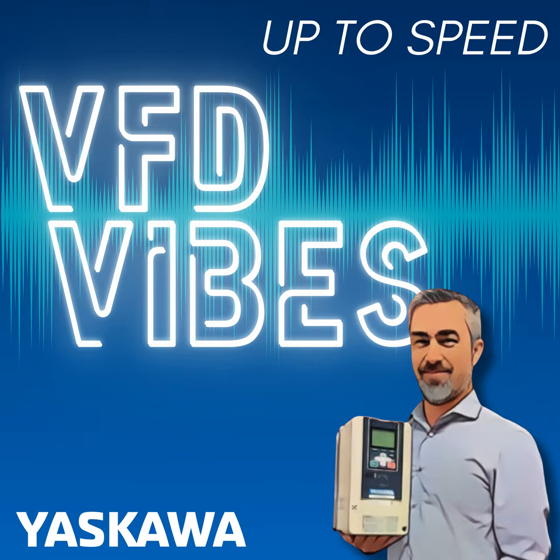S1 and SN, a maintained contact closure on the HVAC drives, will give you a forward run command, and some of the industrial drives as well. Now, the speed reference is sent externally from a signal generator of some sort, typically maybe a PLC controller.